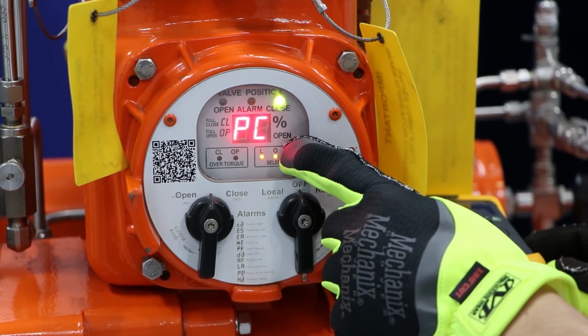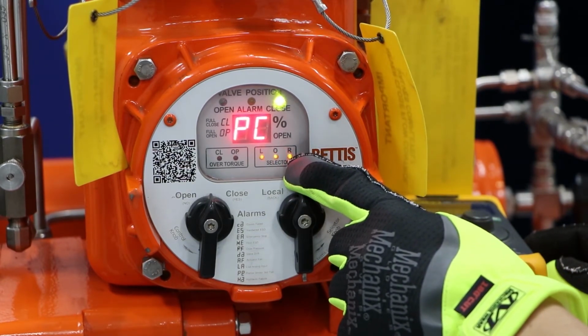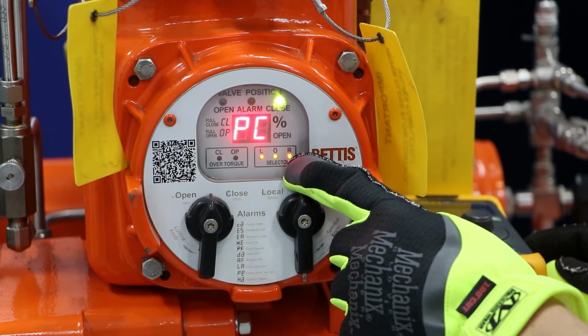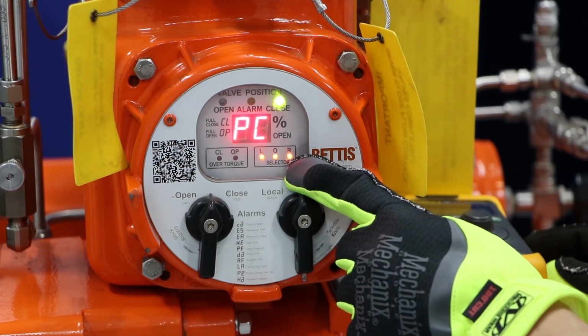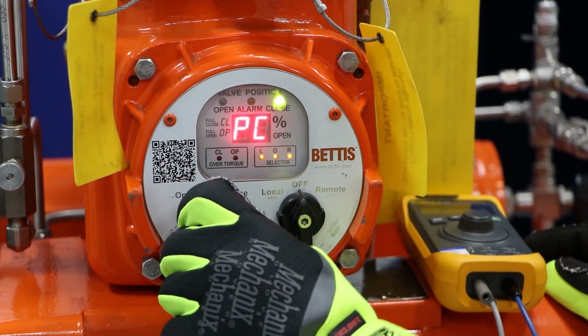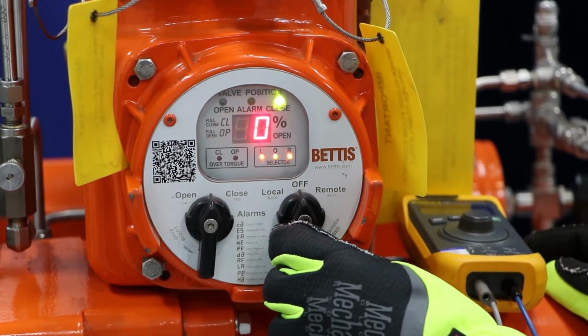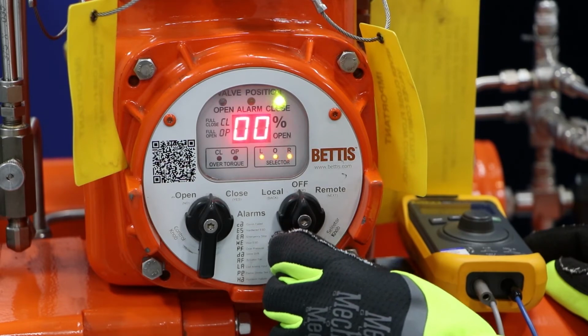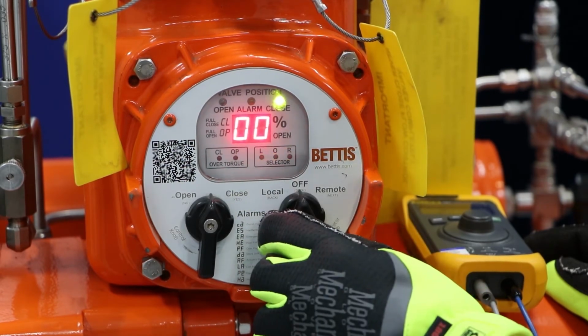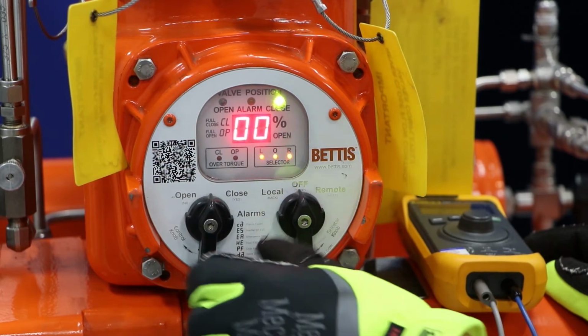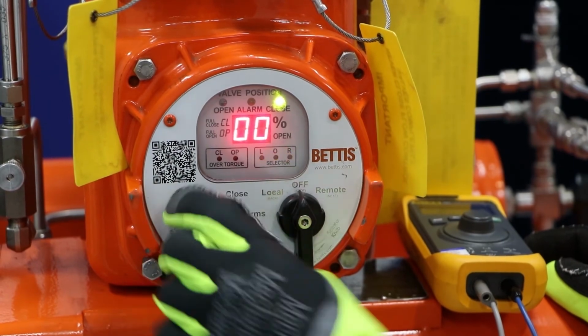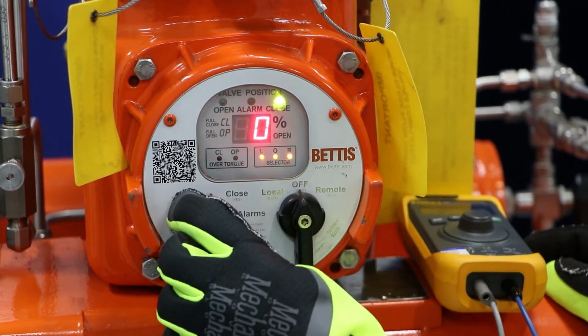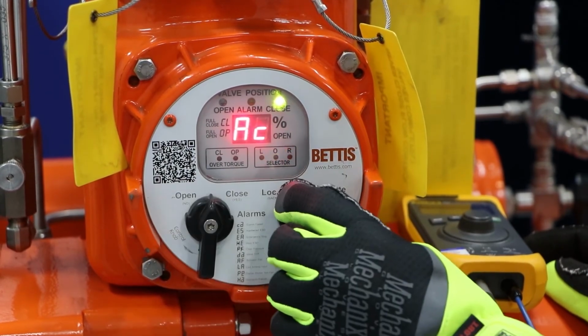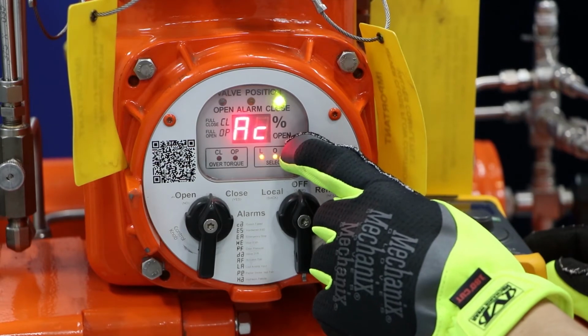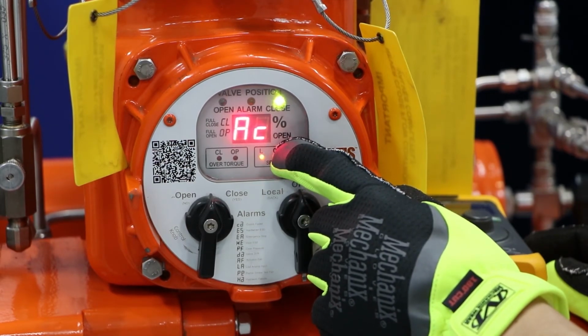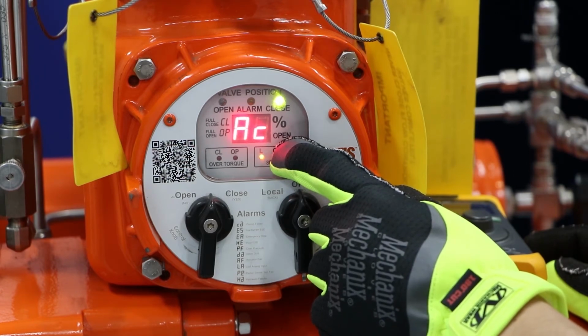The next is the passcode. On the EHO, there's a passcode on every unit. For this unit, our passcode is 0000. Consult the factory and consult your IOM manual to determine your passcode. So we hit yes. It's going to be a 4-digit passcode, and it's going to enter 2 digits at a time. So we're going to enter the thousands and the hundreds digits first. In this case, our passcode is 0000, so we'll hit yes again. Now it's going to ask us for the tens and ones digits, and we hit yes, and we hit yes. If the passcode is successfully accepted, you will see AC appear on your screen. If the passcode is not accepted, you'll see a request to enter the passcode again.